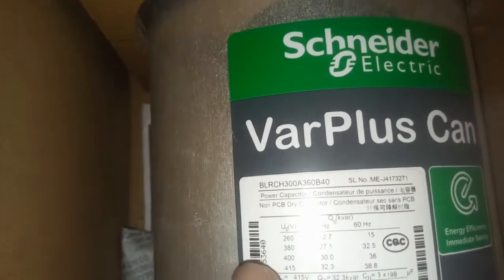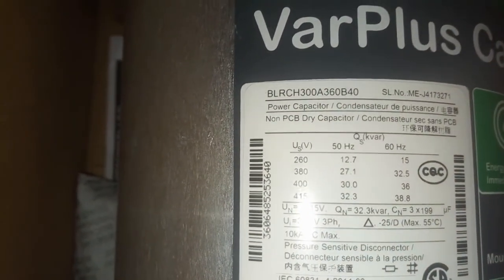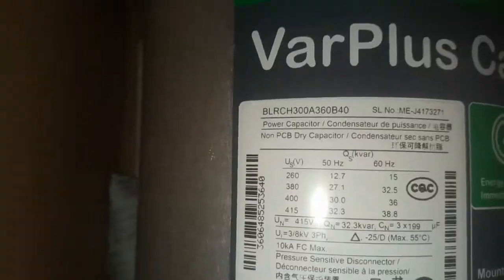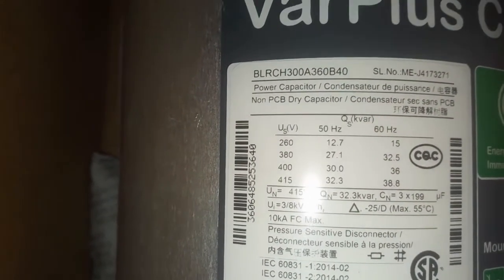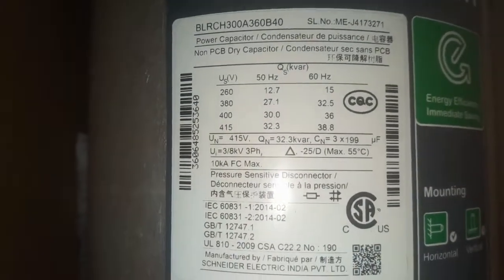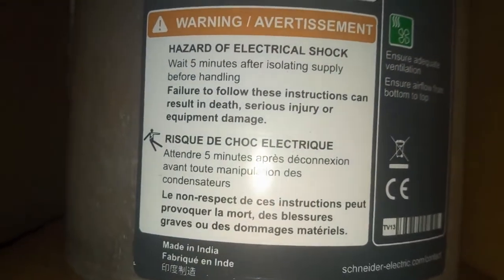As you can see, it is a new one with the inscriptions on it. You have the various voltages: at 260V you get 12.7 kvar at 50 Hz, and at 415V you get 32.3 kvar at 50 Hz. Read everything there and follow the instructions.